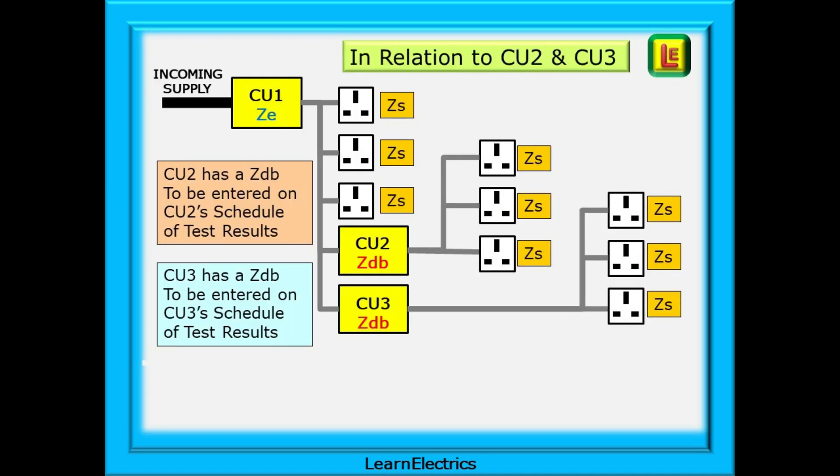In relation to CU2 and CU3, how do we enter the data? We will look at CU2 and CU3 will be just the same. We've had a ZS value for CU2 on the previous slides. This ZS will be entered as a ZDB on the top of CU2's schedule of test results. The socket circuits coming from CU2 will all have their own R1 plus R2.